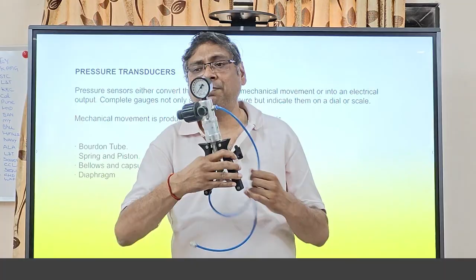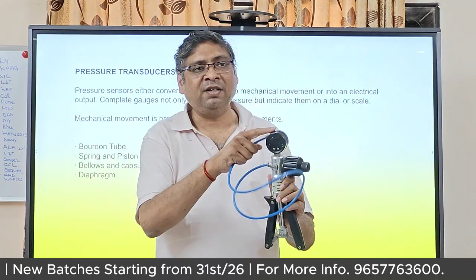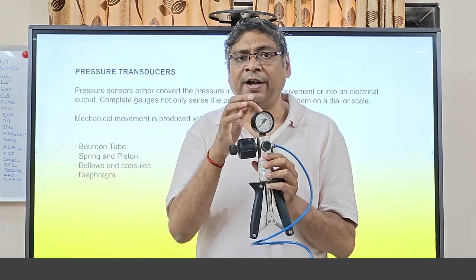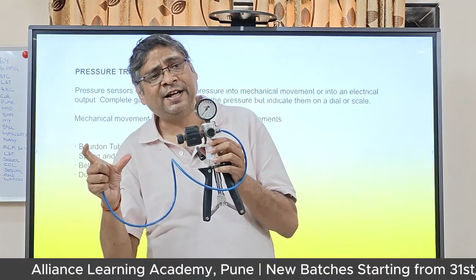What does the Bourdon tube do? When I give a pressure, this is a pressure pump. It is used for the calibration of any pressure transmitter or gauge. What we do here is put a standard pressure transmitter, and here we put whatever gauge is under test. This is the master, this is the test, and with this pump we can build a pressure, with knobs for coarse and fine. We give, like, 4 kg per square centimeter on the master. That should be the same here. If it is not, by their accuracy we can check whether we can use this gauge further or not. If it is a transmitter, then we can do the span and zero adjustment also. In fact, many mechanical pressure gauges have that zero adjustment.